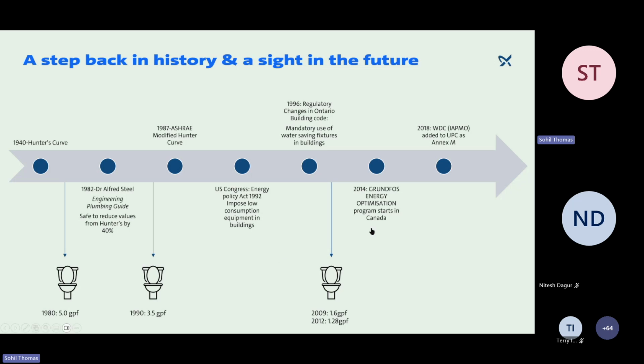So what Grundfos has done to cater to this is that we have started the energy optimization program in Canada, where we identify the load profiles and the flow profiles for different buildings, and we use that database to right size the pumps for engineers, consultants, and whoever wants to retrofit different boosters when it comes to those kinds of sizings. And also, as you can see, the water demand calculator from IAPMO was added to the Uniform Plumbing Code in 2018, which is helping engineers size it better as compared to what we were doing a couple of years before.